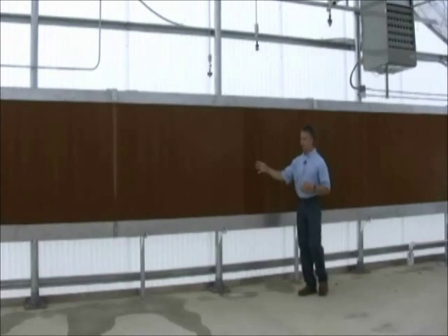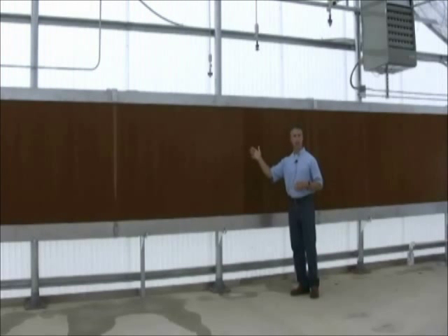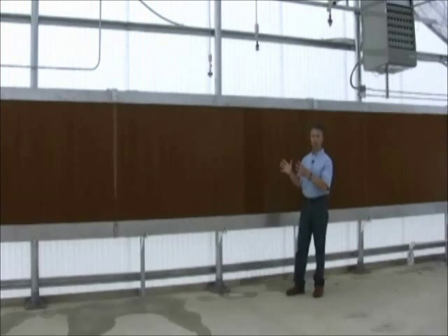Primarily the maintenance of the systems. These systems have to be maintained. The pads have to be cleaned, they have to be treated for algae, the water quality needs to be kept to a certain point, filters have to be replaced and cleaned. So maintenance really becomes a key issue with this system, and how well you maintain it, like so much of equipment that we deal with, it depends on how long the system lasts.